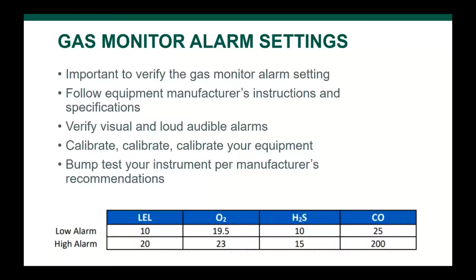And also, depending on the manufacturer, the equipment requires manufacturer calibration either annually or biannually. You have to check those requirements for your pieces of equipment and send those for calibration to the manufacturer so it's in good shape. Also, you have to bump test your instruments according to the instructions. Using the calibration gas, you can just bump test it and make sure that all the alarms are sounding and everything is working.